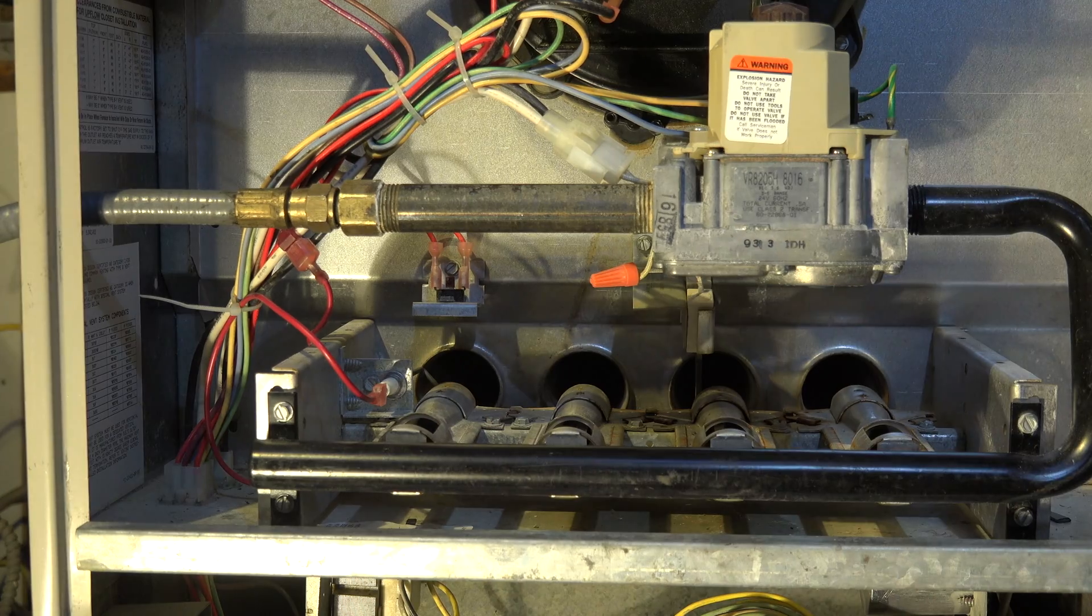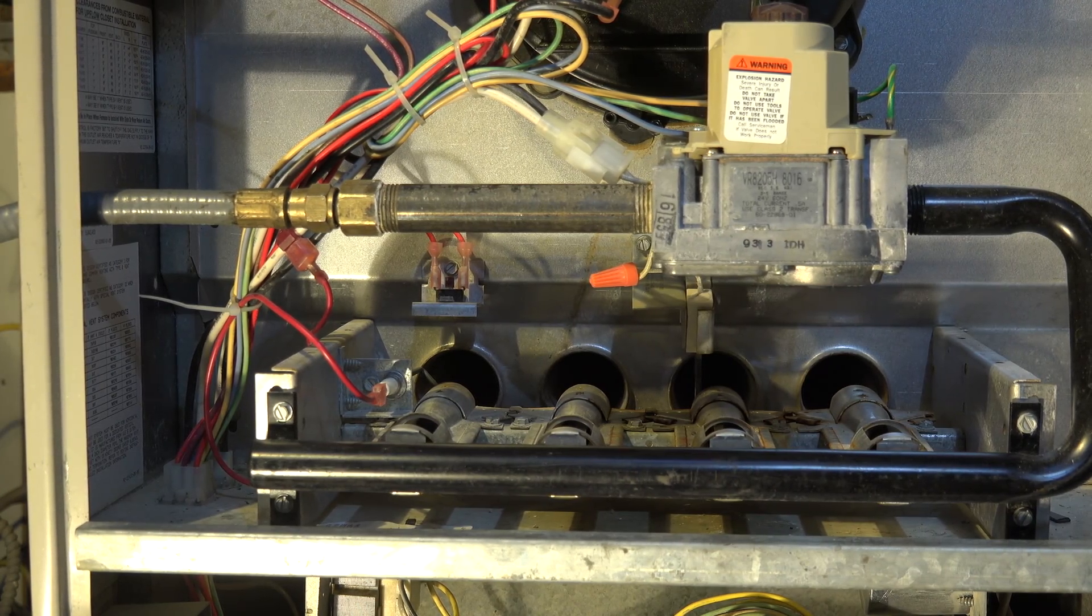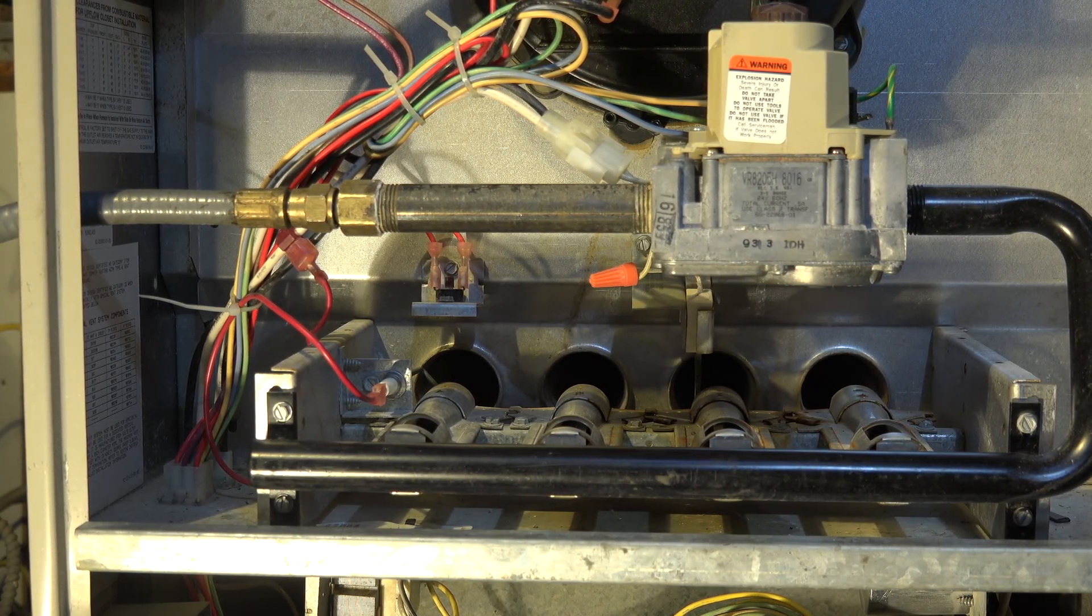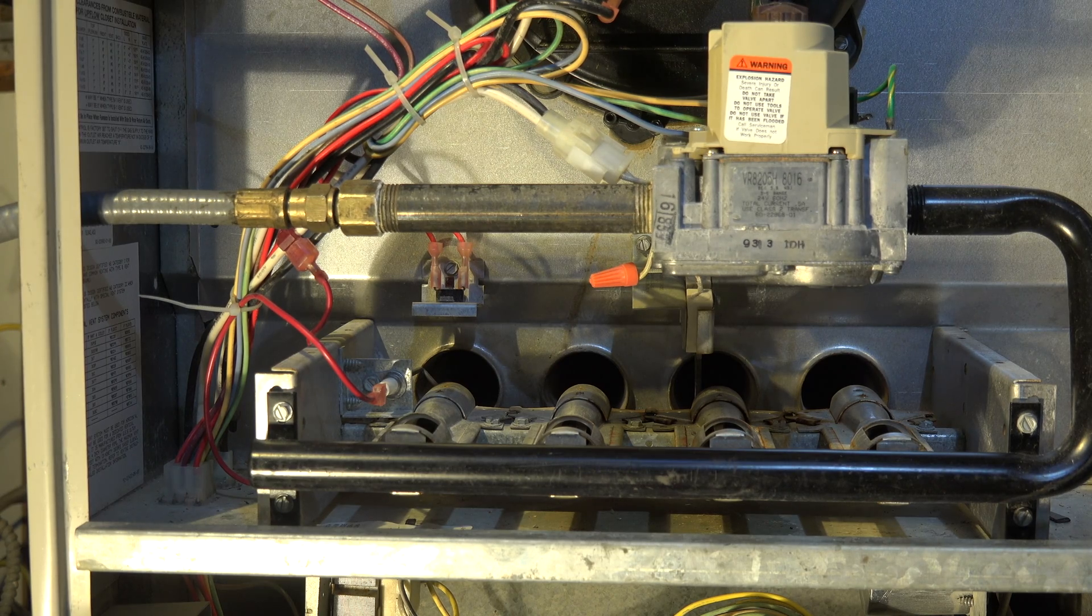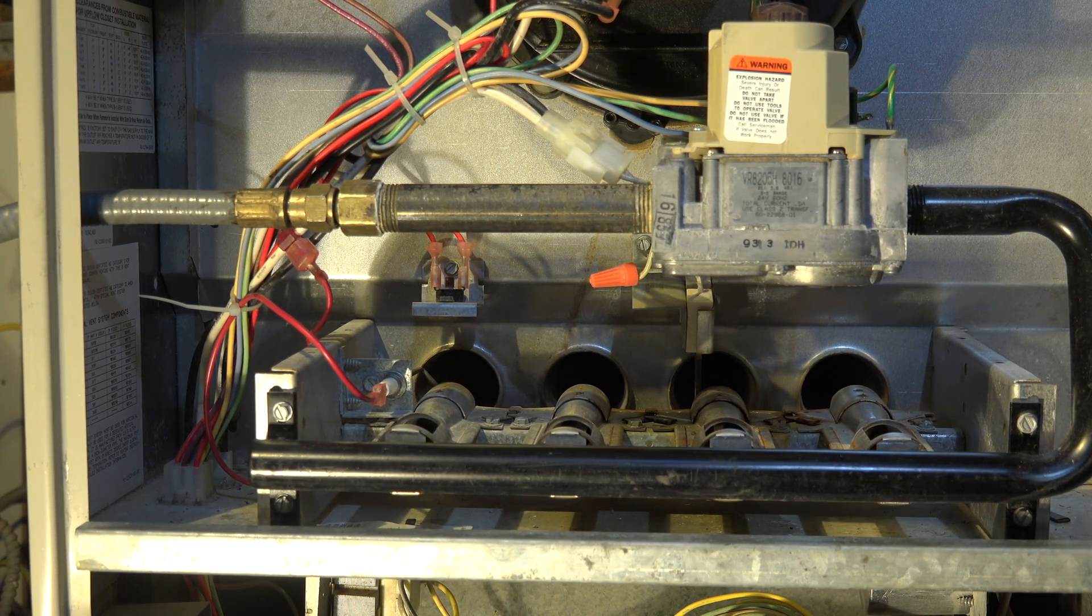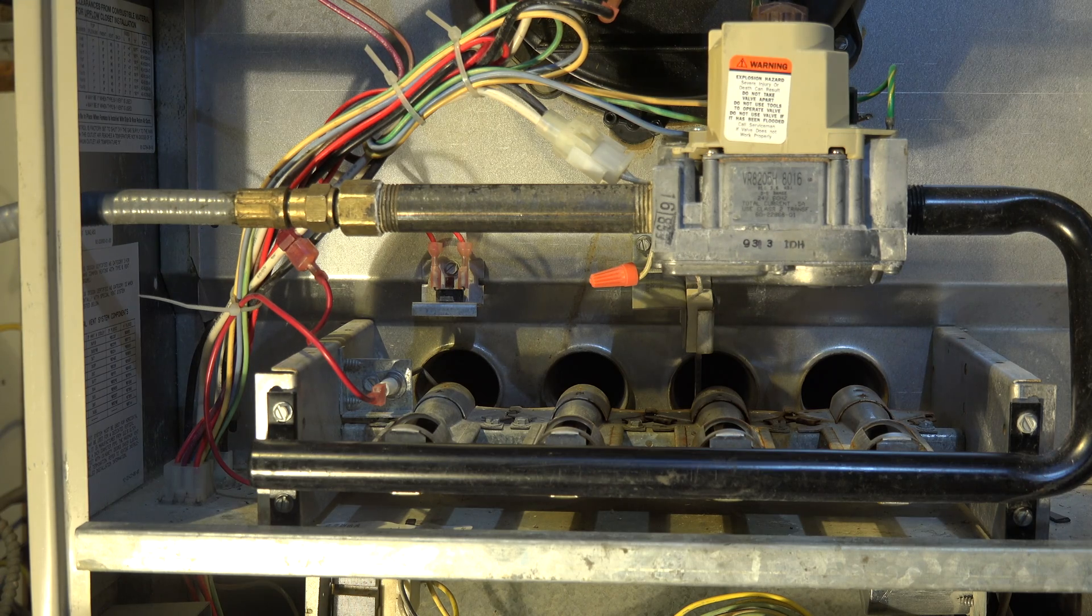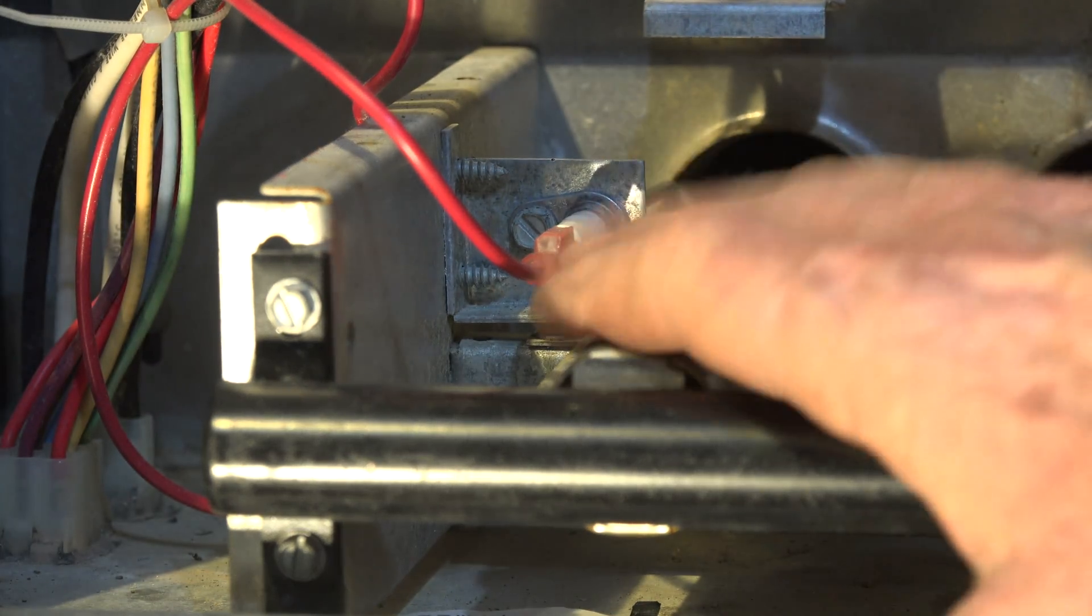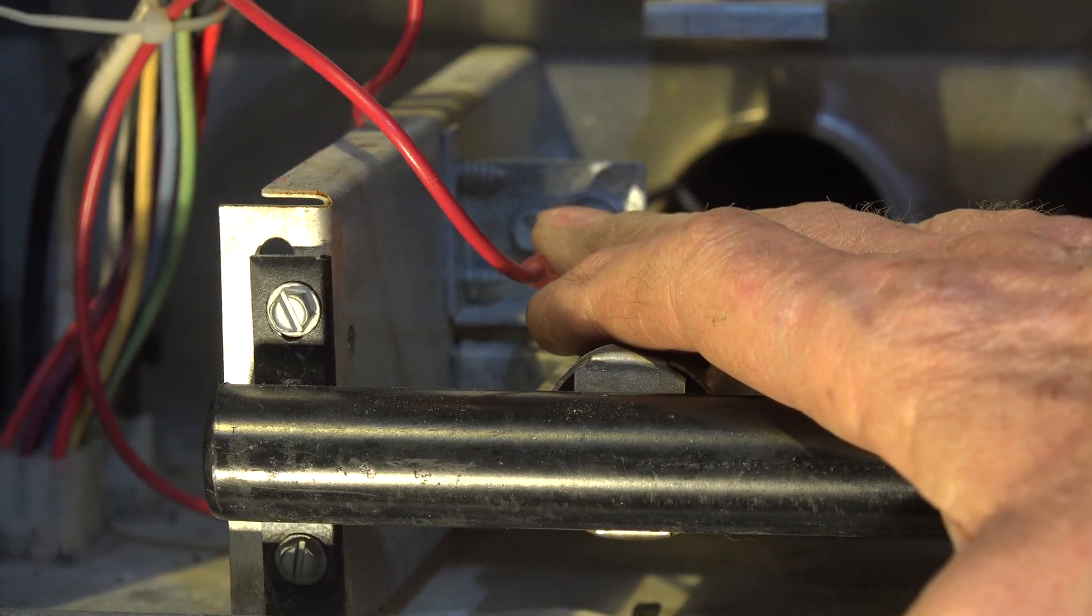Well there's a flame rod over here. Well this thing used the hot surface igniter as the flame rod. But it was not real effective. You had nuisance trips. They gave us absolute fits for a while. So what they did is they gave us this aftermarket flame rod.